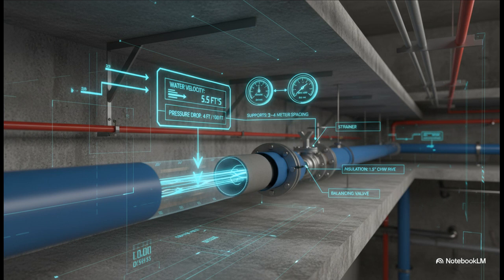They also have to calculate how much pressure is lost over distance to make sure the pumps are the right size. And all along the way, you have these key components: strainers, valves, sensors that keep the system clean, balanced, and healthy for decades. All right, so our chilled water has been created, and it's traveled hundreds of meters through the building. We are now at the finish line.